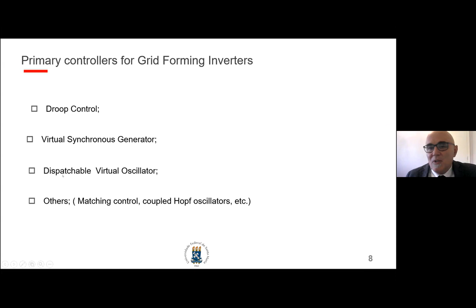Let's move on to Droop Control. Probably most of you know what Droop Control is. It's connected from the voltage and current at the point of connection, it computes active and reactive power, then links active power with frequency through the droop coefficient M, and also links reactive power to the amplitude of the voltage through another droop coefficient. So it behaves similar to a synchronous machine.